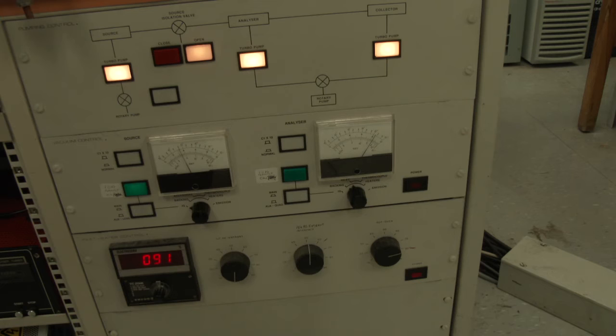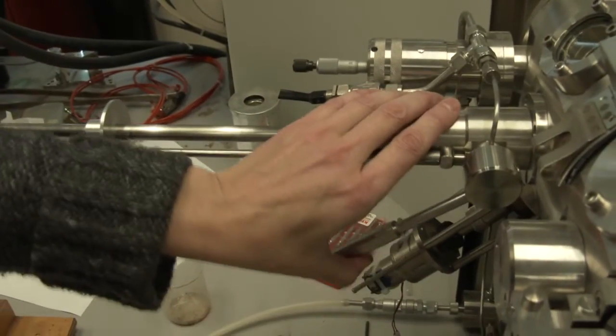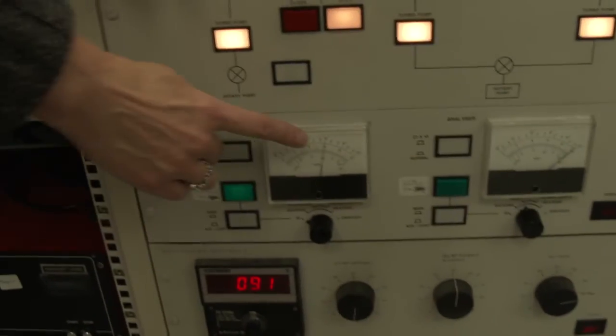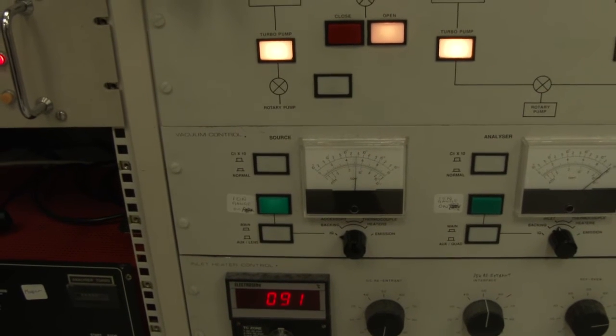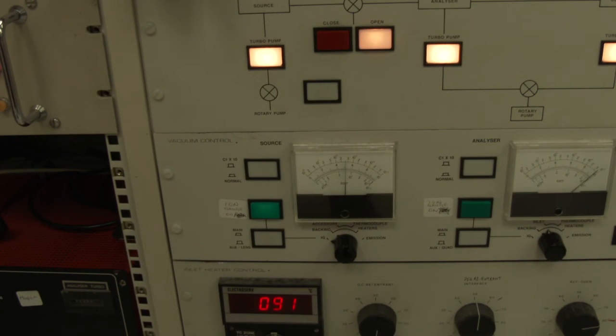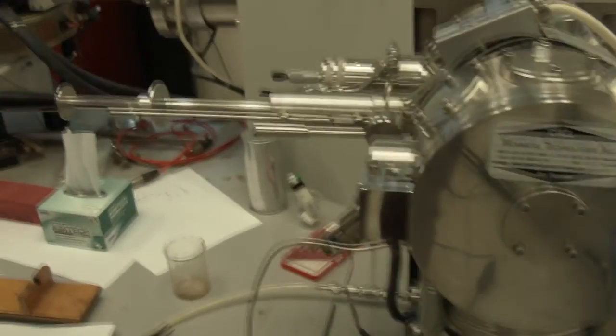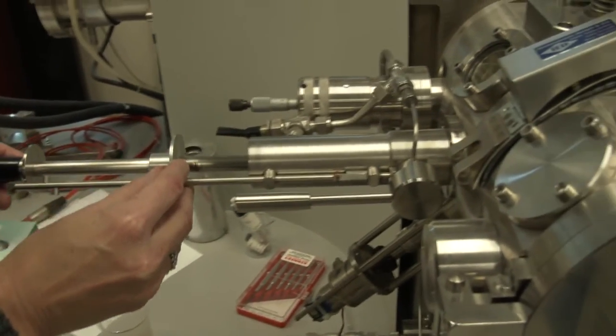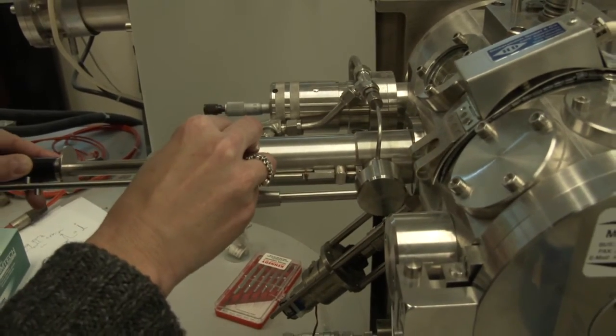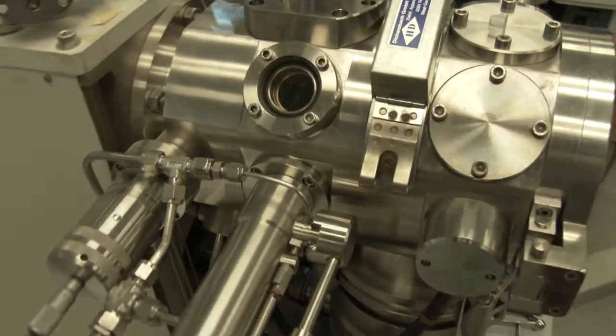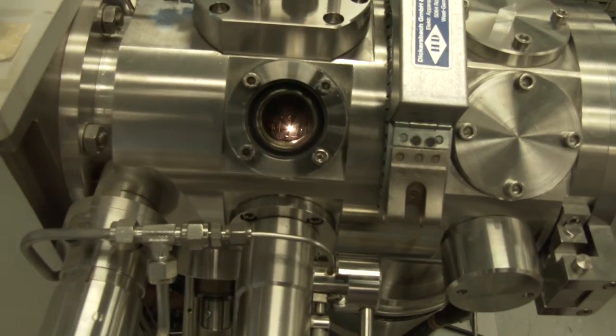This section is now pumped down to approximately 10 to the minus 3 millibar, and the gate between the source and this section can now be opened. The source ion gauge can be seen to increase because of the sudden increase in pressure in the source region due to the difference in vacuum between the roughing pump vacuum and the source vacuum, achieved by a turbo pump, of 10 to the minus 7 millibar. Once the gate is open and the pressures have stabilized, the probe can be inserted into the ion source block, and this can be adjusted and monitored through a window in the side of the source housing.